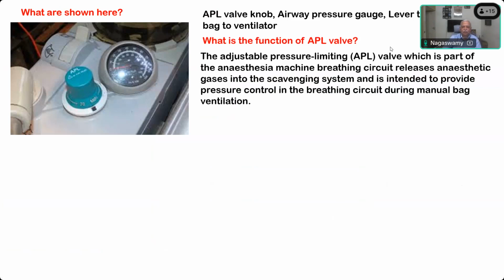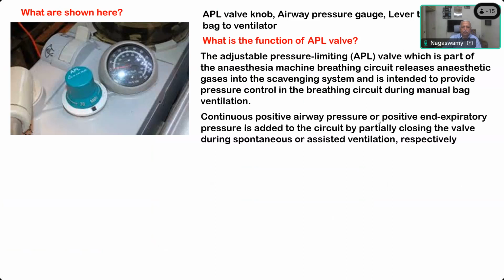So this is the amount of pressure that can be generated. The adjustable pressure limiting valve in the anesthesia machine circuit releases gases into the scavenging system and reduces the internal pressure in the breathing circuit during controlled ventilation. Continuous positive airway pressure or positive end expiratory pressure is added to the circuit by partially closing the valve during spontaneous or assisted ventilation respectively.